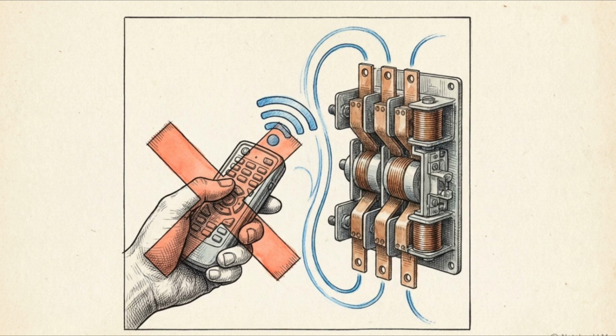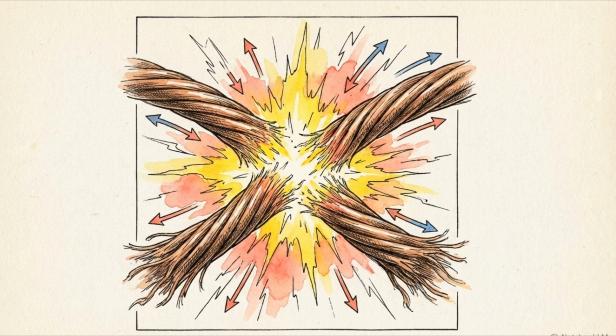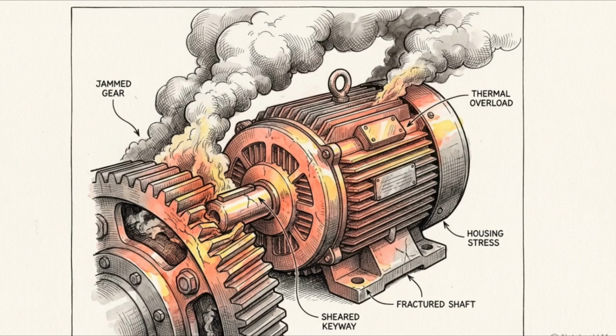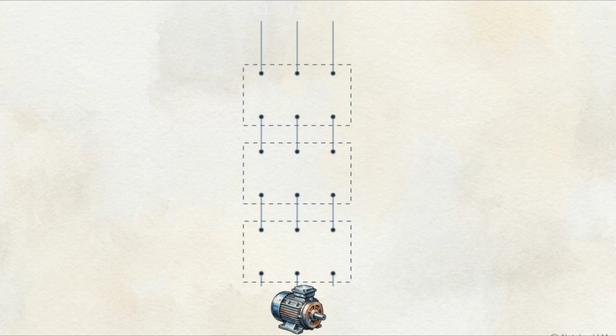First, we need a way to turn a lethal high-voltage system on and off without ever physically touching the circuit. Second, we must defend the entire electrical circuit against a catastrophic short circuit that can flood the system with energy instantly. Third, we have to protect the motor itself against mechanical failures that cause current to rise slowly, generating intense heat over several minutes. The standard three-phase motor wiring diagram acts as the integrated framework designed to address these three variables in a single, repeatable circuit. By building this topology from the ground up, component by component, we can see the exact logic behind every layer of defense in the circuit.